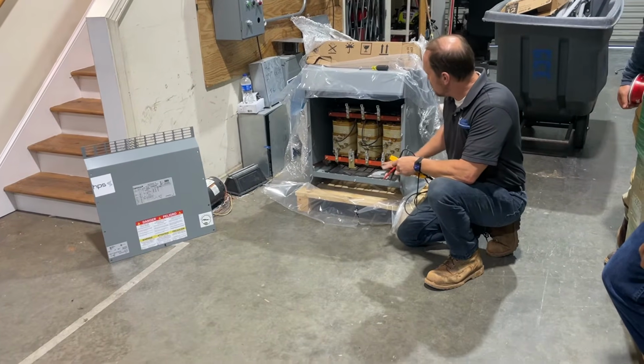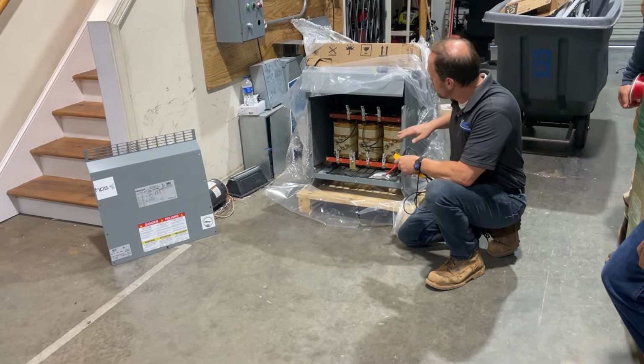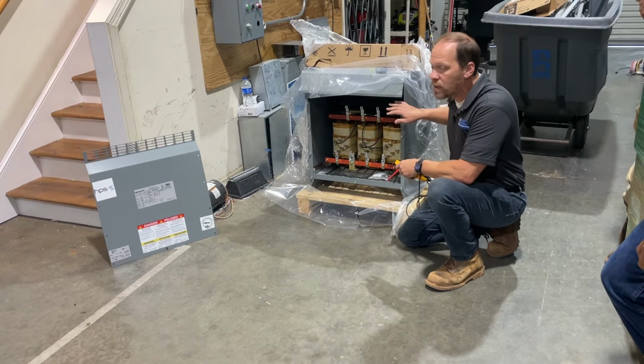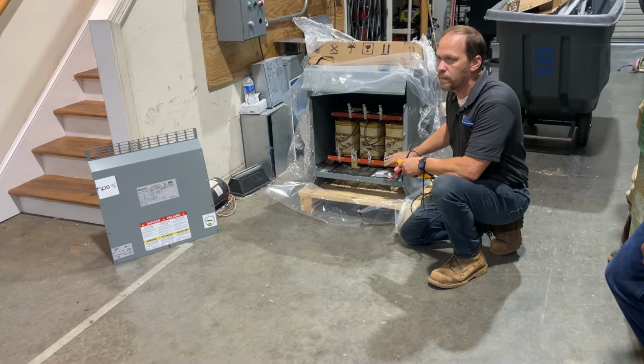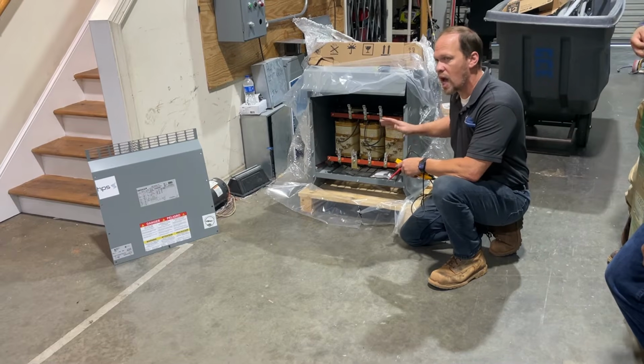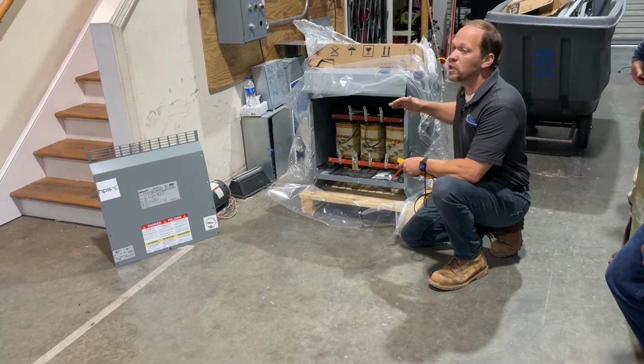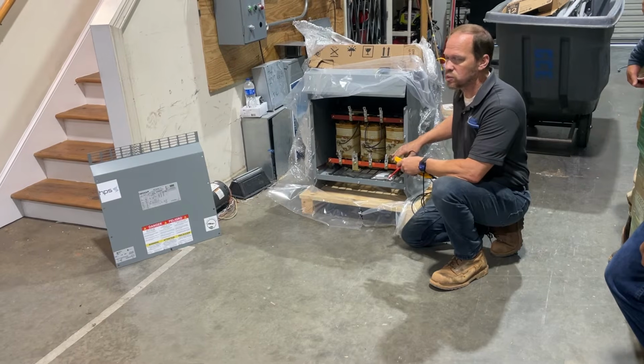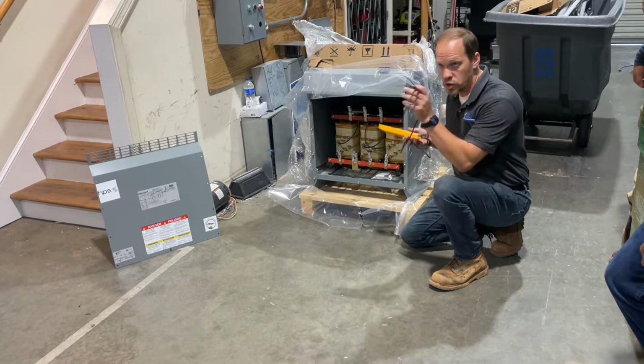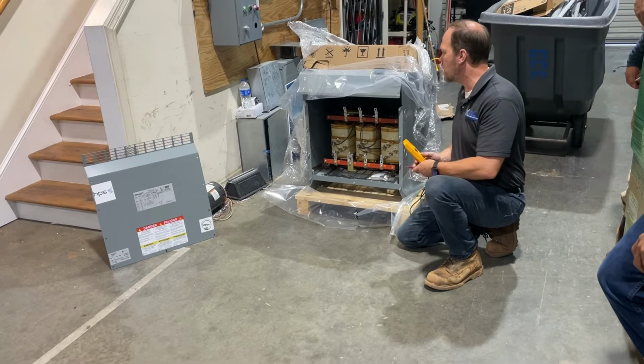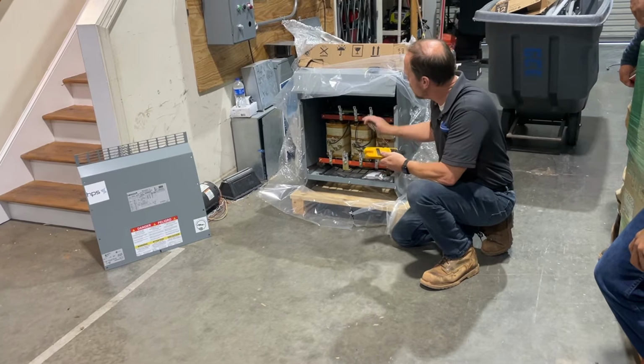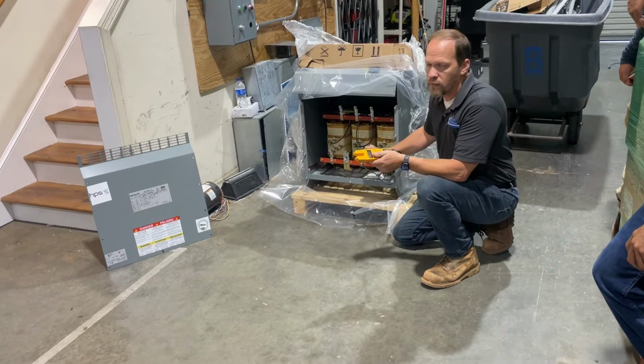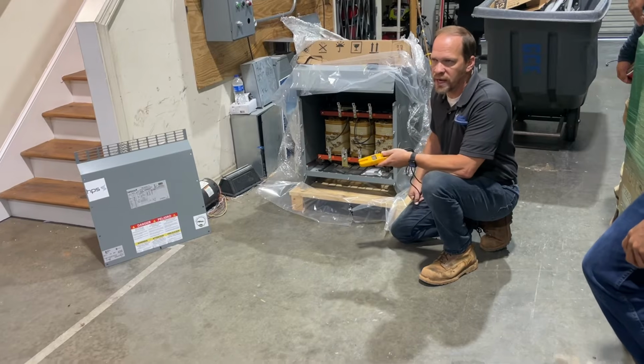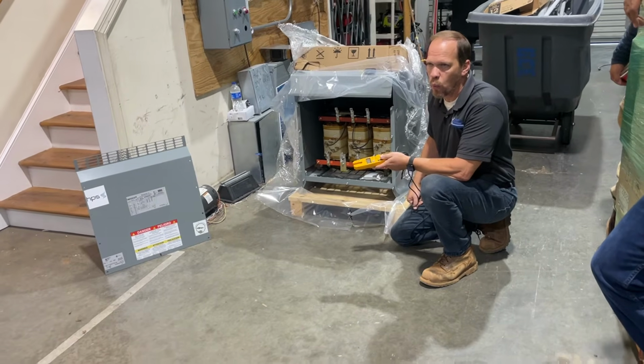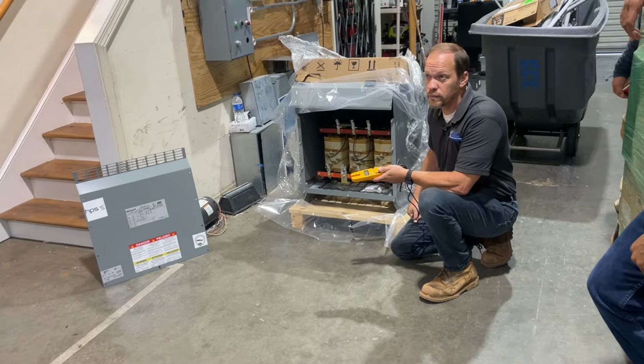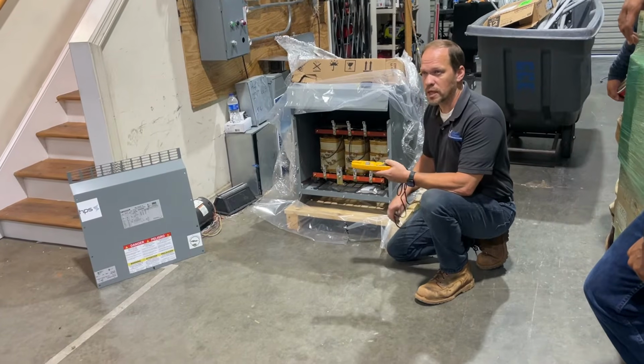So on this particular one, you've got 240 volts on the primary and 480 volts on the secondary. Most of the ones we deal with are just the opposite. We come in with 480, usually we come out with 208. And this one, Jonathan is actually going to install this bad boy, and he's going to be coming in with 240, and it's going to have 480 coming out. Now, we talked about winding ratios. What's our winding ratio here? 2 to 1. Because it's 480 and 240.